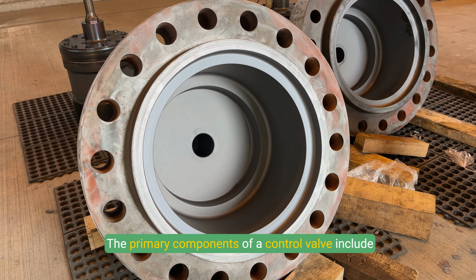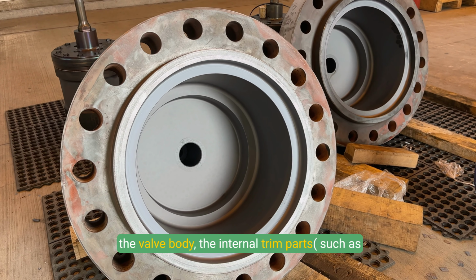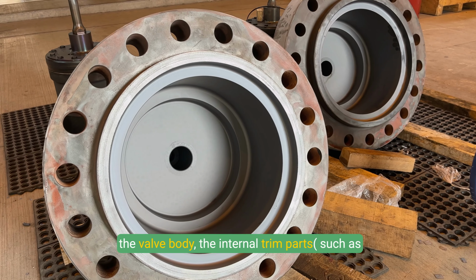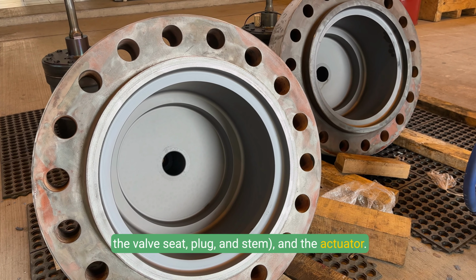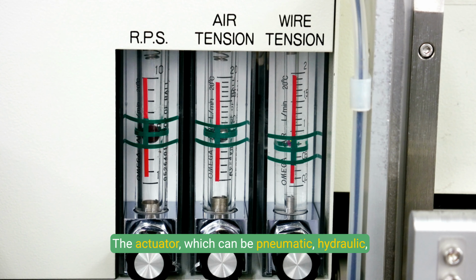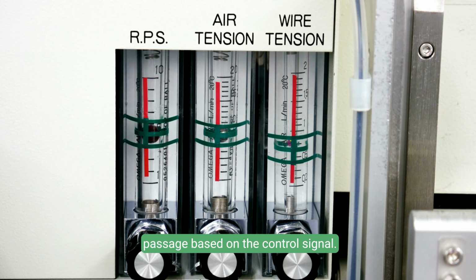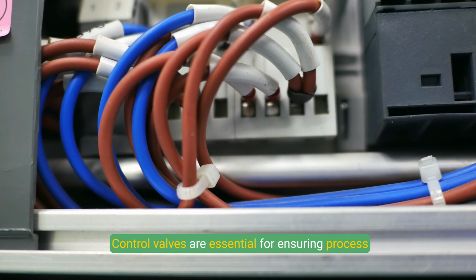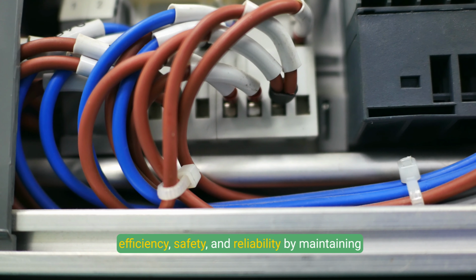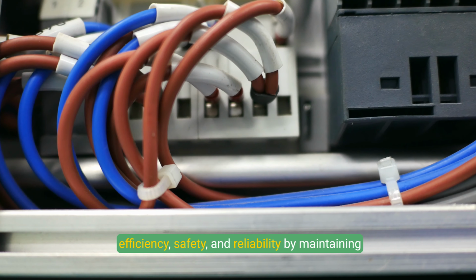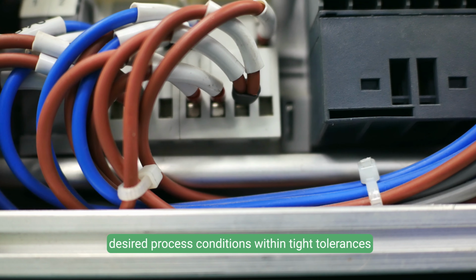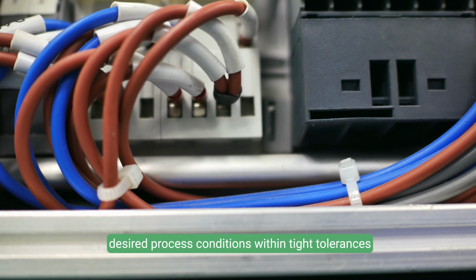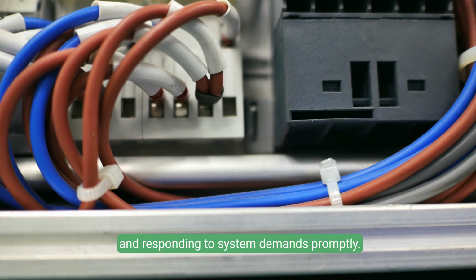The primary components of a control valve include the valve body, the internal trim parts such as the valve seat, plug and stem, and the actuator. The actuator, which can be pneumatic, hydraulic, electric, or manual, is responsible for moving the valve's internal components to adjust the flow passage based on the control signal. Control valves are essential for ensuring process efficiency, safety, and reliability by maintaining desired process conditions within tight tolerances and responding to system demands promptly.